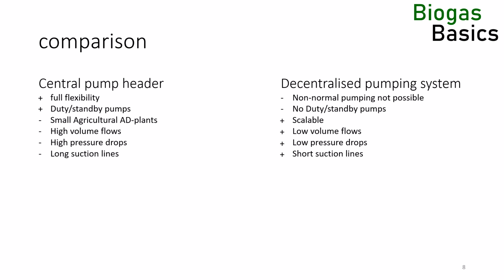Furthermore, the gas bubbles add an elastic property to the digestate. Instead of pumping digestate, the pump will simply deform it if the gas holdup becomes too high. Considering all those effects, the suction lines on digestate pumps should be as short as possible. A direct consequence of this is that centralized pumping systems only work for low viscosity applications. If the digestate has a high viscosity, a decentralized pumping system is the only feasible option.